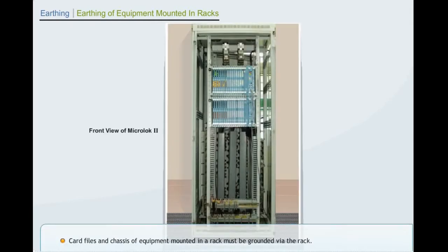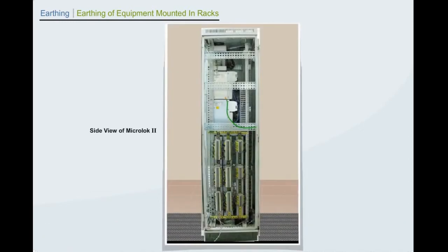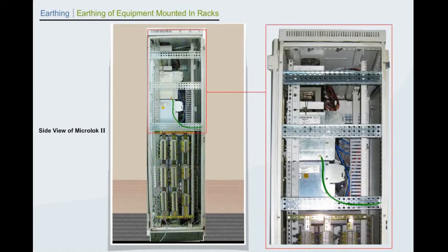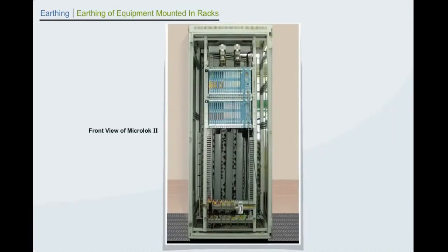Earthing of equipment mounted in racks. Card files and chassis of equipment mounted in a rack must be grounded via the rack. This can be done by connecting the ground stud on each card file or chassis to the rack using 4 square mm insulated copper wires. Terminate this wire on the rack frame.